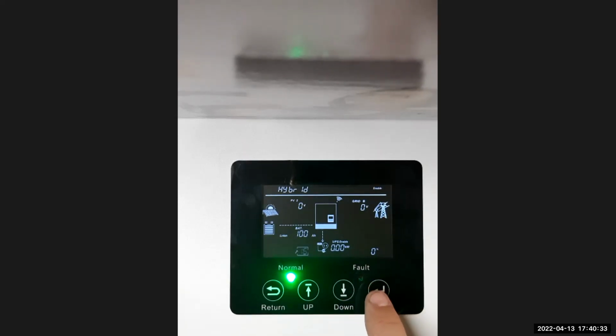But if you enable your hybrid function, you also have the option to feed back into the grid. If you want to feed back into the grid, you enable that function as well. And you can tell it the maximum amount that's available from the panels after the output of the battery, that panel power will be fed into the grid. That's the hybrid function on the screen as I explained it on the computer as well. This is just for working with the battery. You're never going to play with 17, so you leave 17 as it is.